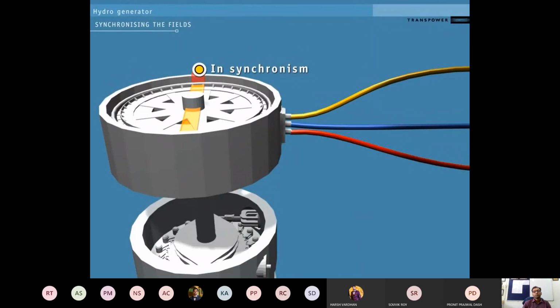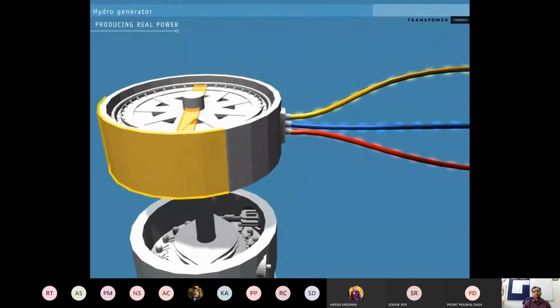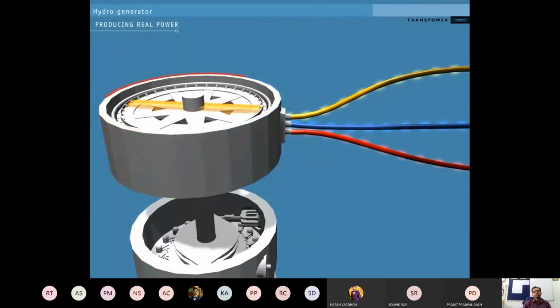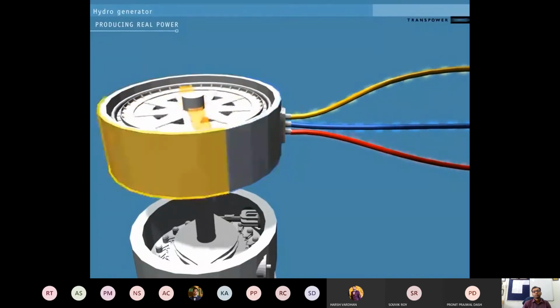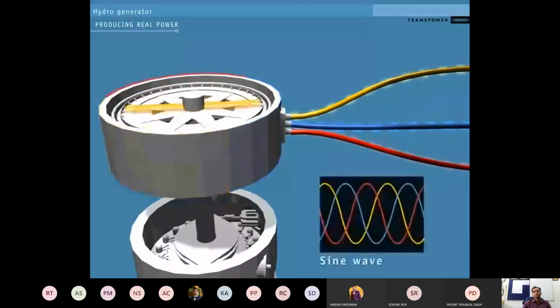System conditions can push the stator's magnetic fields out of sync with the rotor. The difference between the movement of the stator's magnetic field and the rotor's is the torque angle. The rotor has many electromagnets on it, producing a consistent flow of power. The generator produces 3-phase power by using different conductors to carry the power generated along different parts of the stator, as shown here. This creates a 3-phase alternating current, which is represented by the sine wave.